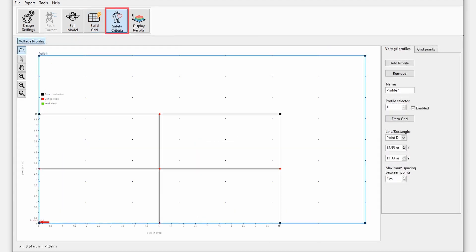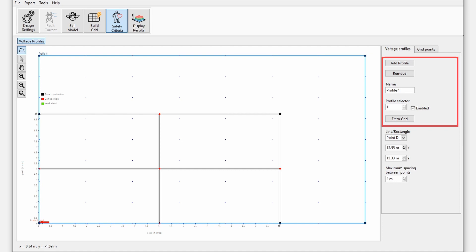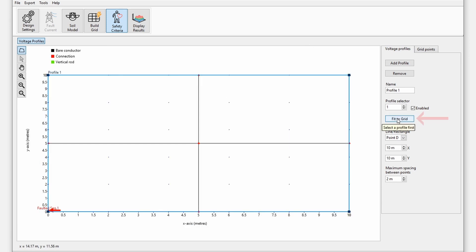Next in the safety criteria module, we will add the voltage profiles. Voltage profiles specify the locations where the actual surface and touch voltages will be calculated. With the voltage profile selected, press fit to grid to cover the grid area. Change the maximum spacing between points to be 1 meter, which is a reasonable spacing for the size of the grid.